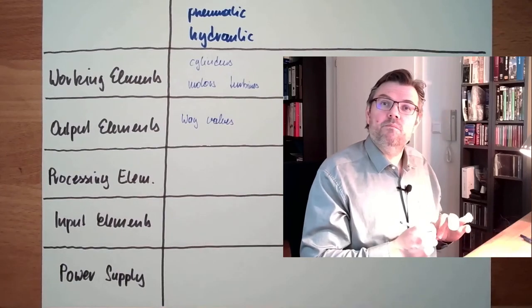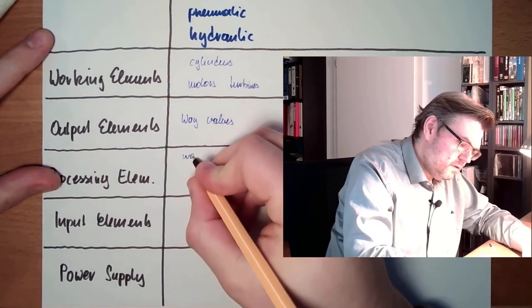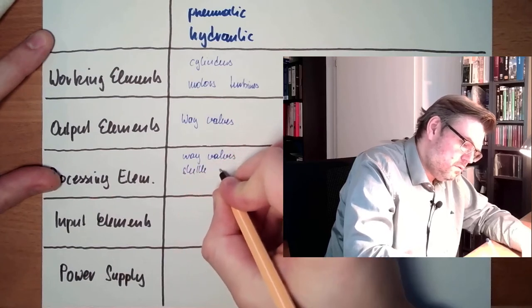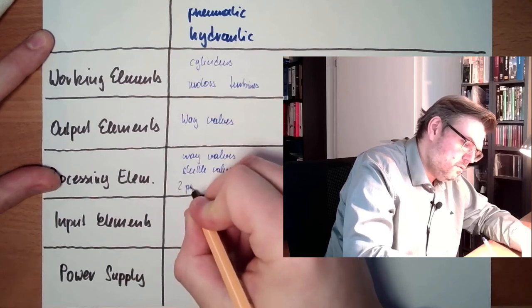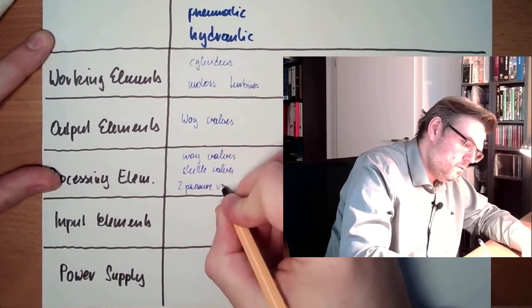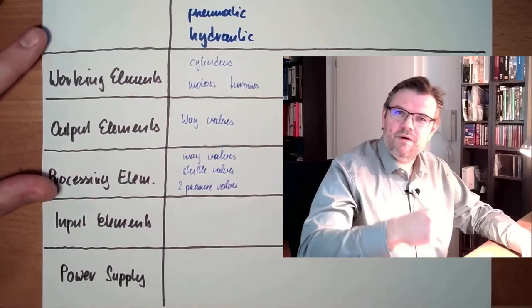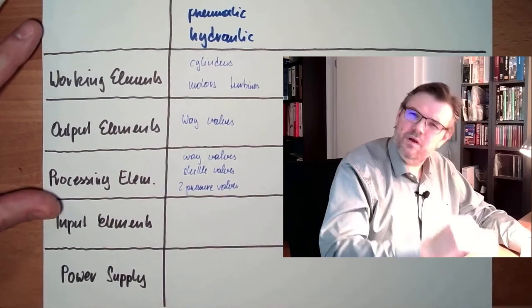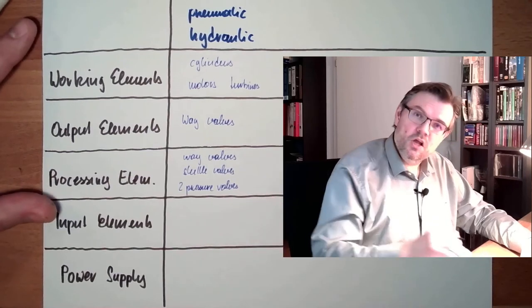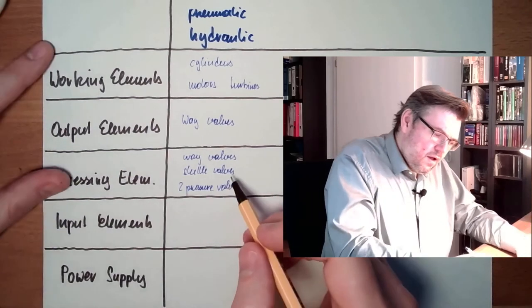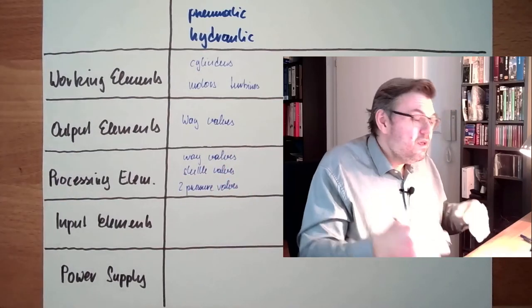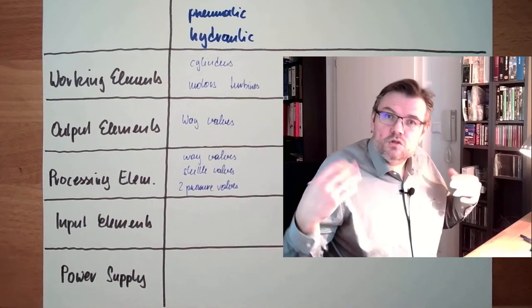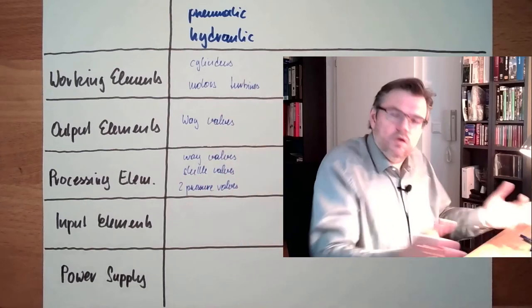Then there are process elements. This might also be way valves, shuttle valves, two pressure valves, pressure control valves, check valves, non-return valves. Process elements, doing the logic, realizing the logic. They are usually smaller, tinier, and whatever is the outcome will then switch, usually if it's a pure pneumatic or hydraulic control, they will switch the way valve, which is operated pneumatically or hydraulically, and the cylinder does its job.